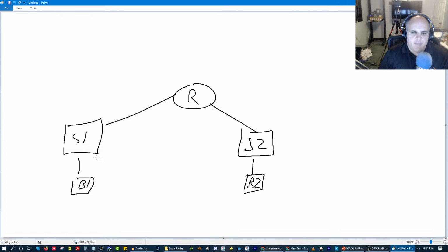Now, if BAS 1 wants to communicate to BAS 2, and BAS 2 is on subnet 2, and this is on subnet 1, then what has to happen is in this router, there needs to be a route that says, oh, to reach subnet 2, you go out this port. Now, if we want a broadcast to reach subnet 2, there's really nothing we can do. And you say, but Phil, there actually is. And that's with BACnet. And I would say to you, yeah, you're absolutely right with BACnet, but IP traffic in and of itself, broadcasts are not going to travel.